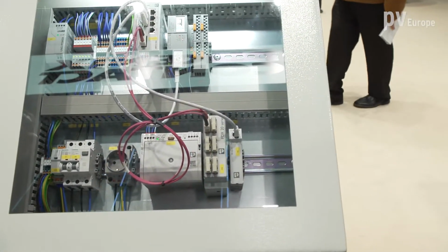You already presented this device 2 years ago, 2019, I guess. So what's really new? We launched this product already 2 years ago, but up to now we implemented a lot of new stuff and optimization. What's very brand new is the so-called multi-instantiation mode. That means you can handle at one grid connection point several energy generation units, like a PV installation with a battery, or a PV with a combined heat and power plant or generator, all connected to one grid connection point with one device. Normally you have to use two devices. Now we integrate this into one, and that's the big benefit on a commercial level for the customer.